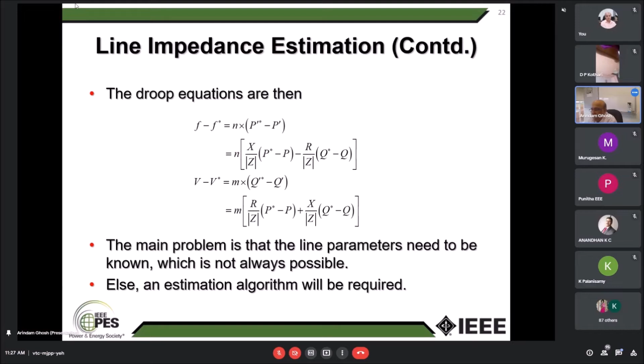Suppose what happens is that you have a system where you have got several DGs and loads. So between, say, one DG and DG1, between DG1 and DG2, there are two loads. In between the loads, the Thevenin impedance will change if the load changes, or the Thevenin impedance between a DG and a load will change if one of the DGs goes out of service.